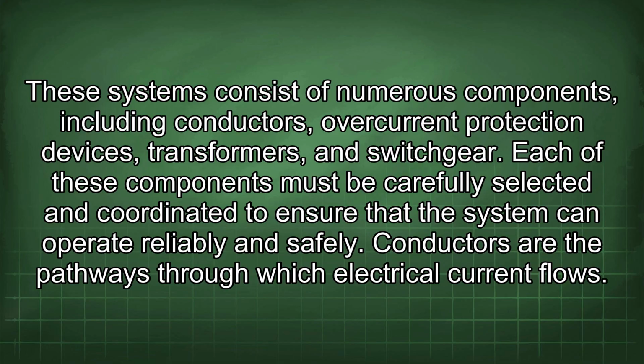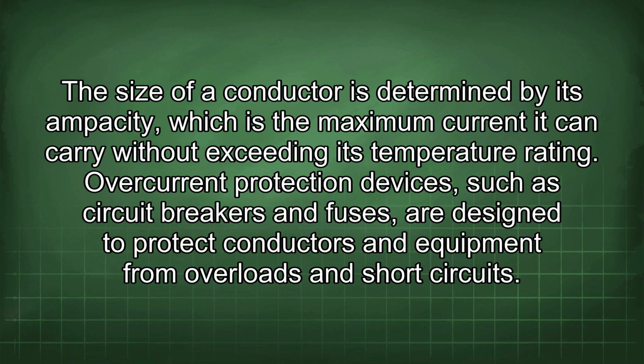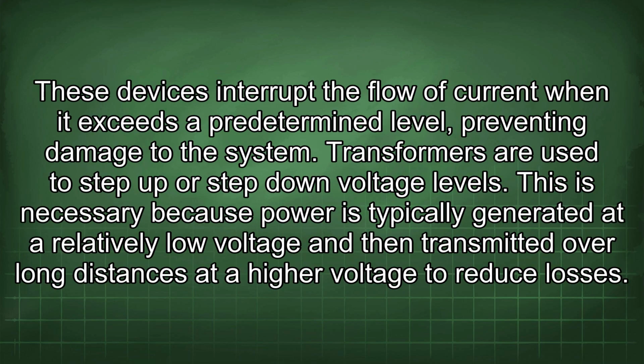Conductors are the pathways through which electrical current flows. The size of a conductor is determined by its ampacity, which is the maximum current it can carry without exceeding its temperature rating. Overcurrent protection devices, such as circuit breakers and fuses, are designed to protect conductors and equipment from overloads and short circuits. These devices interrupt the flow of current when it exceeds a predetermined level, preventing damage to the system.